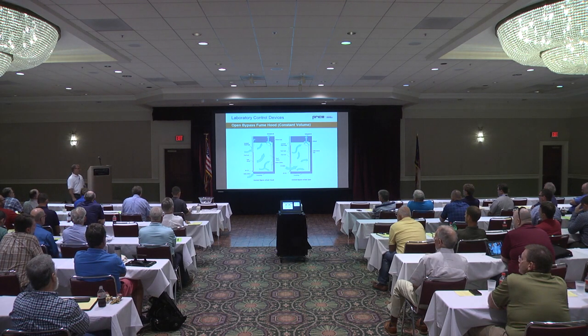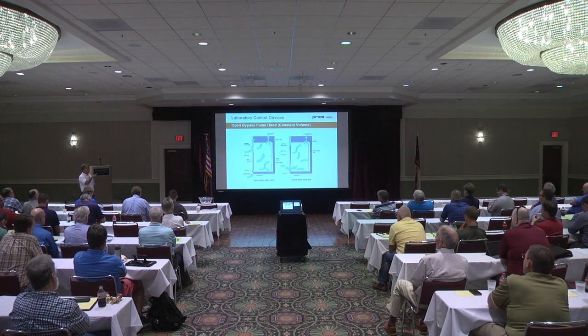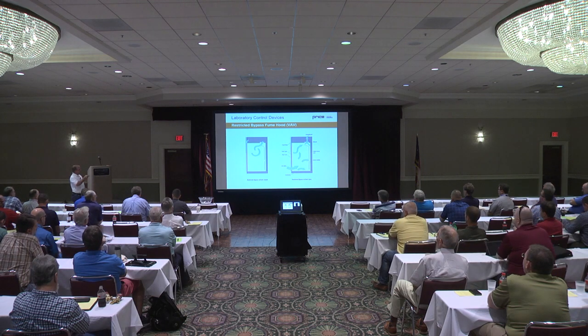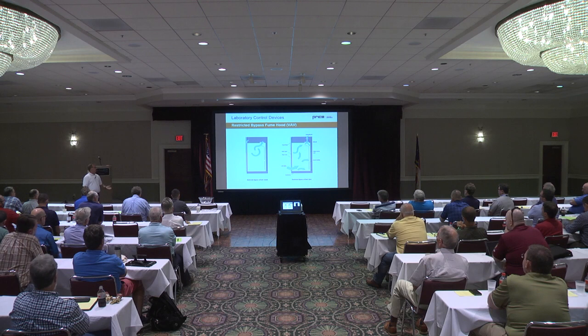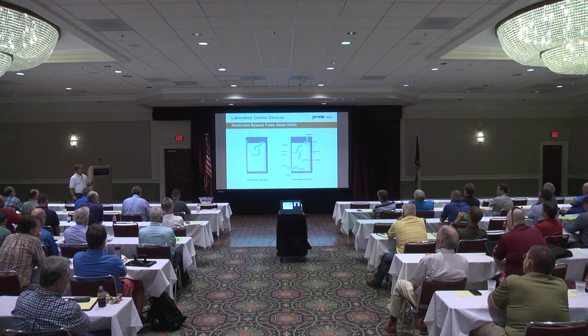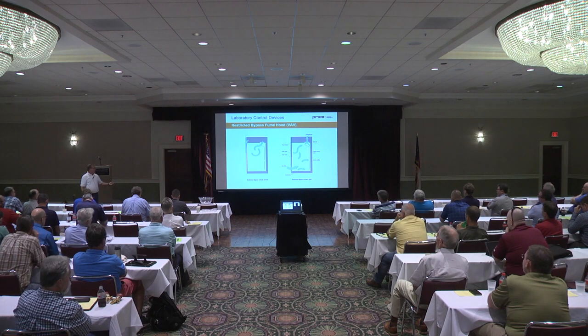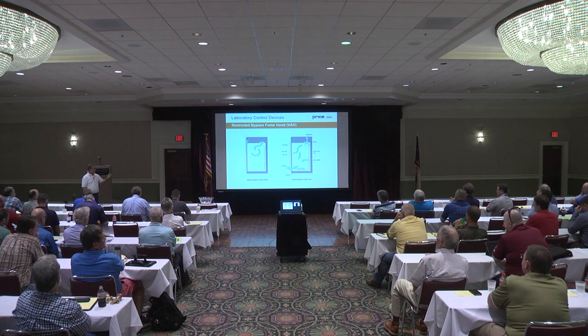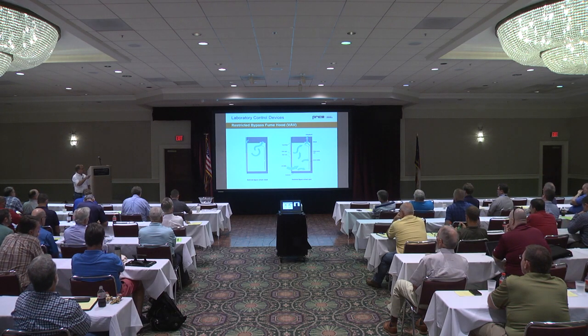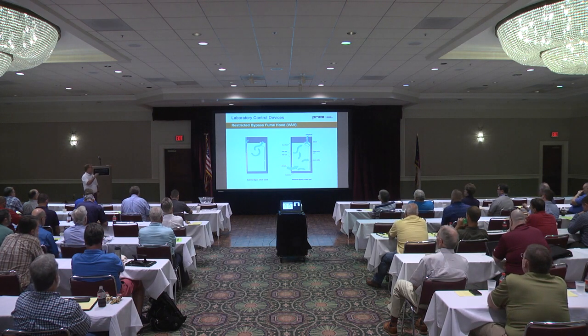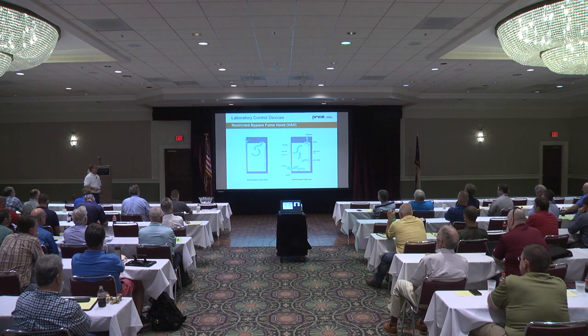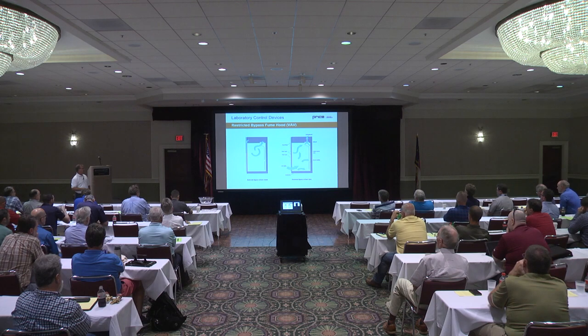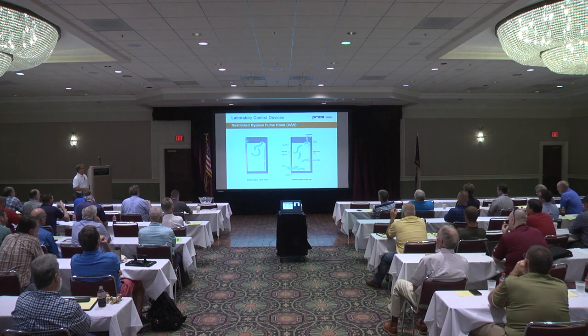So we're going to lose airflow at the top. Normally not enough to prevent the fume hood from performing, but it's something to note that that's in a variable volume application. We're trying to take everything through the sash opening with no losses anywhere, and that louver will cause losses. Such as restricted bypass or a VAV hood. There's no louvers in the top. All the air comes through the sash or through the airfoil at the bottom, allowing for much better, I'd say, containment, with the air coming through the sash when it's open. So you can see the differences here. A lot less airflow or eddy currents in the fume hood when it's closed, and when the sash is open, your airflow is coming through the open area of the sash, maintaining safe fume hood capture in a variable volume application.